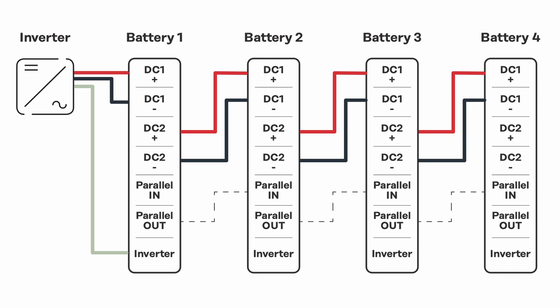After the first one, when you go with the parallel out contact from the first battery to the second battery, in the second battery you're using the parallel in contact to connect the cable, and then from the second battery to the third, again you need to take the parallel out contact to go to the parallel in contact of the third battery, and so on and so forth.